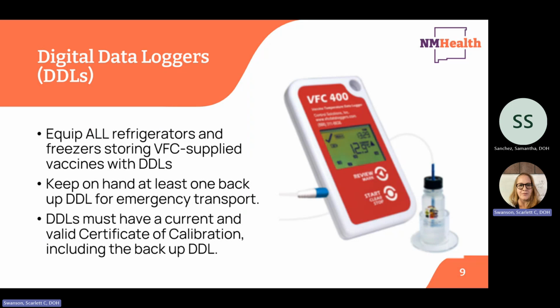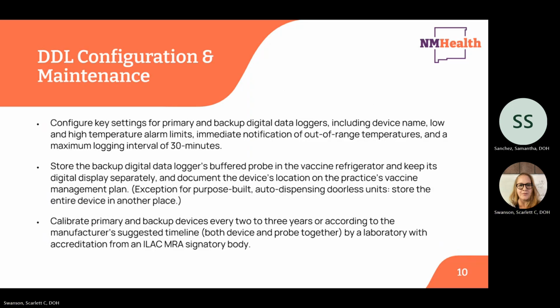Depending on the size of the practice, additional devices might be needed. Digital data loggers must have a current and valid certificate of calibration, including your backup digital data loggers. Configure key settings for your primary and backup digital data loggers, including the device name, low and high temperature alarm limits, immediate notification of out-of-range temperatures, and a maximum logging interval of 30 minutes. Store the backup digital data logger's buffered probe in the vaccine refrigerator and keep its digital display separately. Document the device's location on your emergency vaccine management plan.